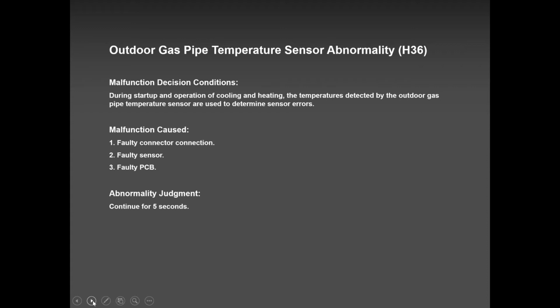And trust me, with these sensors, when a sensor goes bad, the unit will not last for more than 3 minutes. The unit will not run for more than 3 minutes. Okay, James? The unit will not run more than 3 minutes before it shuts down if it is a sensor issue.